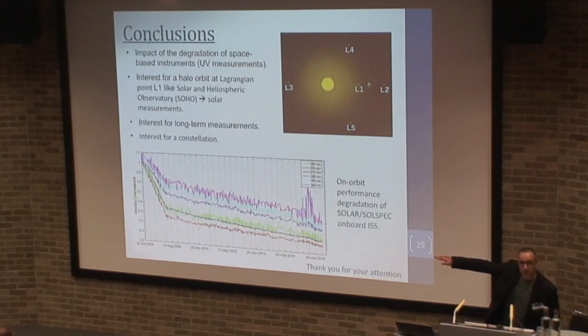Just looking at this degradation plot, there are 2 trends there. Do you have any explanation what has changed to slow it down? Yes, good question. For the first trend, we use the internal calibration lamp inside, something like a halogen lamp. When we use the lamp, there is a high temperature variation, and this has an impact on all the glue inside the system, so we have fast outgassing. After this step, we switched off the use of the lamp, and after you can see the impact of the degradation is lower. So operation is very important when you do long-term measurement, and you can see the impact of temperature and operation on the process.